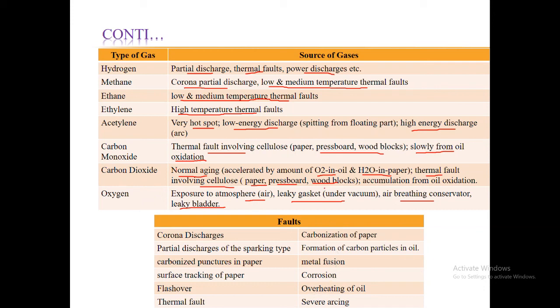So gradually the succession of this partial discharge activity will turn into the catastrophic failure of the high voltage equipment if not prevented. So this is one of the ways to monitor the health of the high voltage equipment on the basis of this dissolved gas analysis, but it is applicable only to those equipment which use the liquid dielectric.